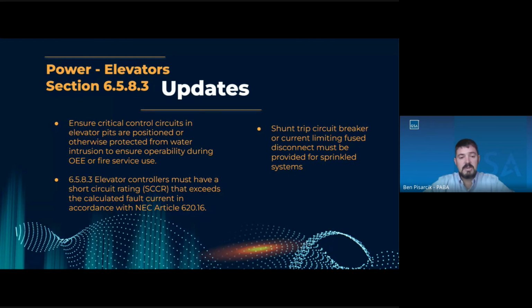And then the last bullet: a shunt trip breaker or fused, or current limiting fuse disconnect, must be provided for sprinkler systems. In the past, it only said shunt trip breaker, and we've included current limiting fuse disconnect for that.